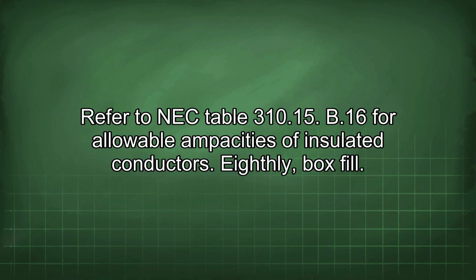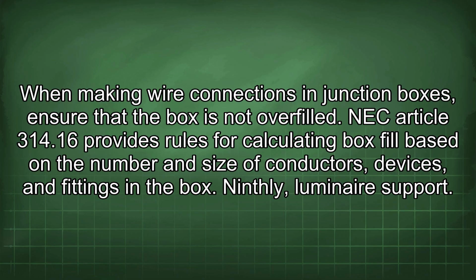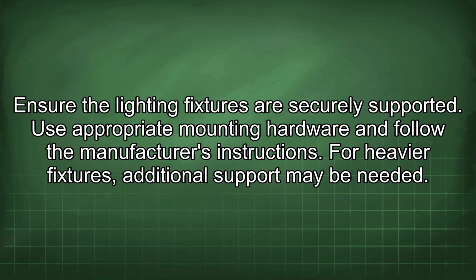Eighthly, box fill. When making wire connections in junction boxes, ensure that the box is not overfilled. NEC Article 314.16 provides rules for calculating box fill based on the number and size of conductors, devices, and fittings in the box. Ninthly, luminaire support. Ensure the lighting fixtures are securely supported. Use appropriate mounting hardware and follow the manufacturer's instructions.